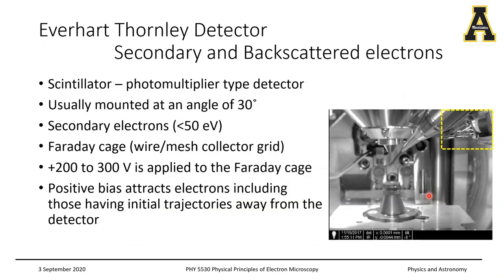One of the most popular detectors is the Everhart-Thornley detector, which is capable of detecting both secondary and backscattered electrons. Let's take a look at where it is positioned inside the electron chamber. You have your lens here, the area where you place the specimen, and the Everhart-Thornley detector marked in yellow. Take note of the metallic cage-like feature on the tip of the detector — this is very important for enabling the collection of low energy secondary electrons. I'll refer to this as the ET detector.